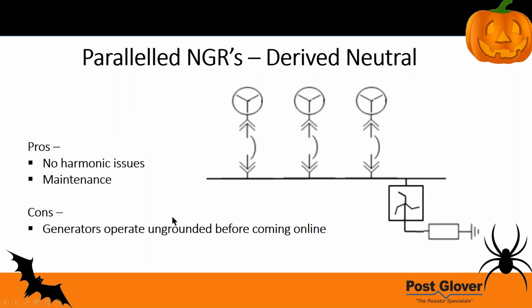Let's go on to the next. So a different way to do this is a derived neutral. What we're doing here, just to describe it, we have the same three generators. In this scenario, it's some kind of a neutral deriving transformer. That's what this box is right here, a neutral deriving transformer. And then because you're on a three wire bus typically, you have the resistor hanging off that.